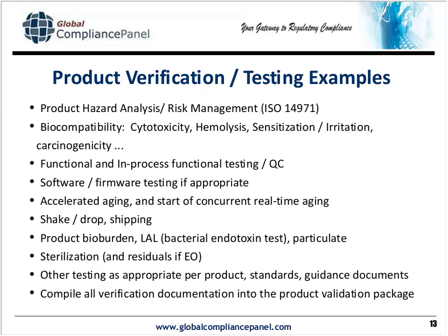Product bioburden issues, LAL, pyrogenicity testing, if you make that claim, particulate testing, if that's a requirement, if it's in the fluid pathway, sterilization issues, and if you have a 510(k) for an ETO sterilized product, you have to do residual testing and put the actual residual data in your submission, gamma, etc. All of this either validated or included under an AAMI Tier 2 analysis to show that your product is better than the worst case product that you have as an example that you validated for sterilization.